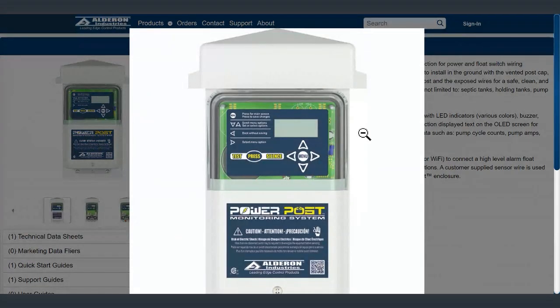And this has an OLED display on it and a menu structure here. So you can do a lot of things with this. This gives you lapse time, event counts, pump run indication. This has multicolor LEDs, so green LEDs when the system is normal, power to your alarm circuit. When the pump is running, there are blue LEDs that flash. On the display, it'll tell you how long the pump has been on, how many amps it's drawing, how many cycles it's run. And then we also have average amp draw of the last 10 cycles, maximum amp draw of the last 10 cycles, minimum amp draw of the last 10 cycles, and then your last count and duration and all that, and then total counts.